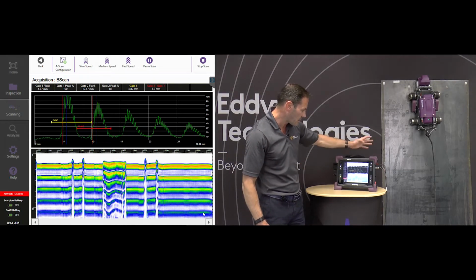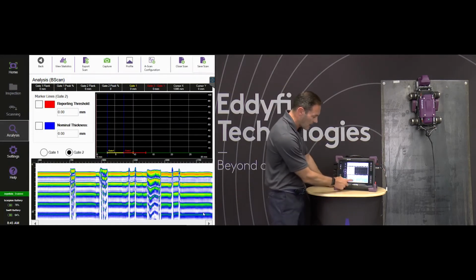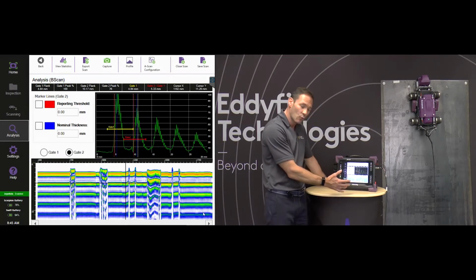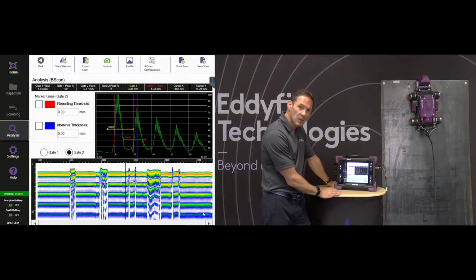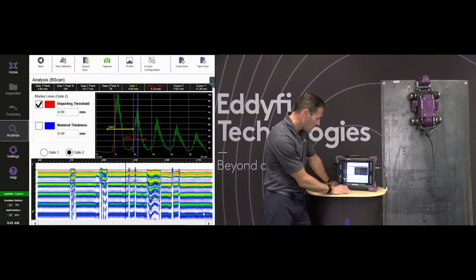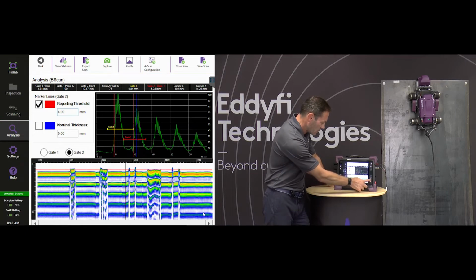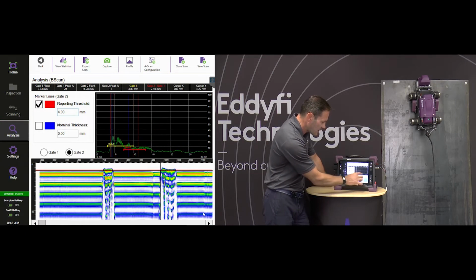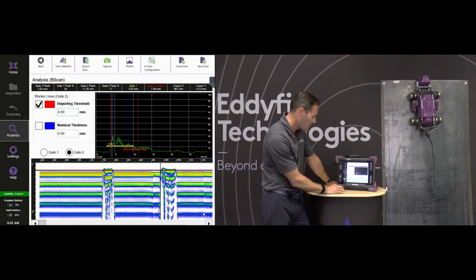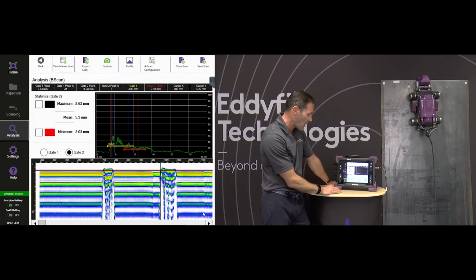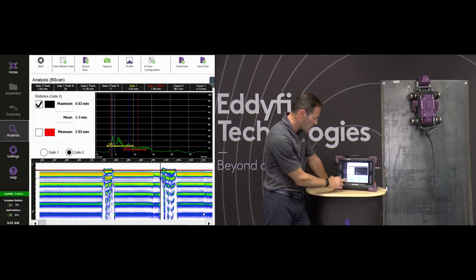So again, I've completed my scan. I'm going to stop my scan. There again is the result. Again, I can do my analysis, look at the individual results of the measurement itself, and also change the result as we go. Then we have the option to input some marker lines where we can say, okay, my minimum is 4 millimeters, and it will draw a marker line, and we can see a little bit better when we zoom in. I can see here that the defect is crossing my marker line, which I've just set here. I could do the same for the nominal thickness. And the other option we have is to have a look at statistics. So we can say, okay, what's the minimum, the average, and the maximum measurement.